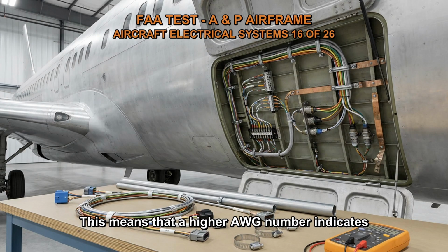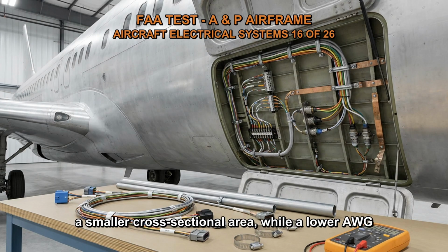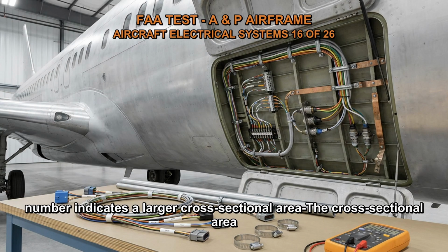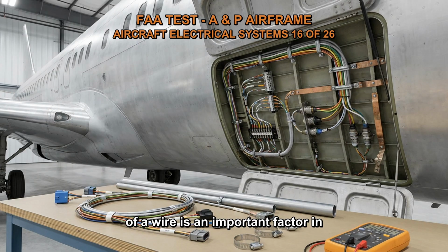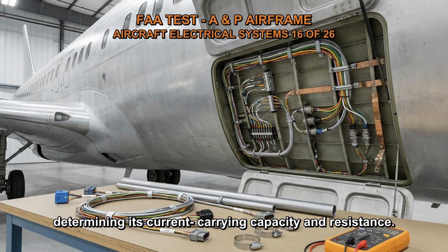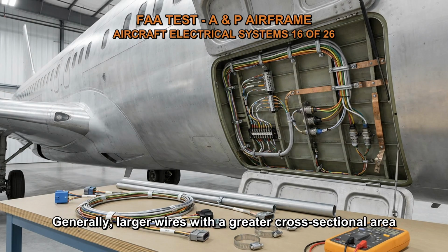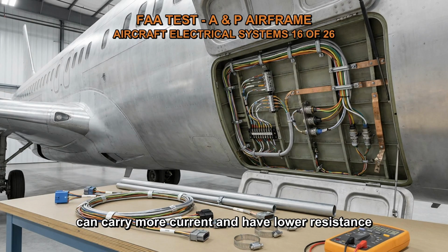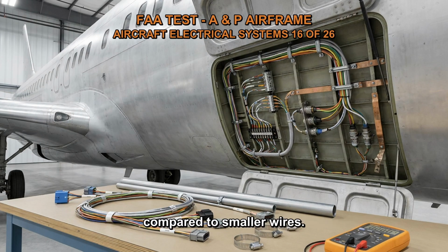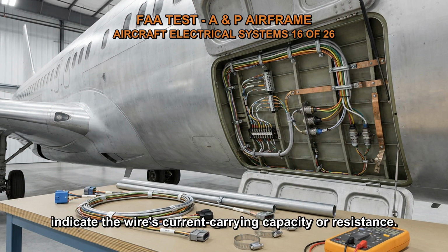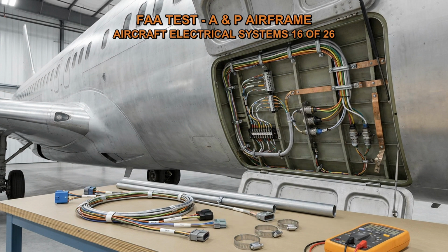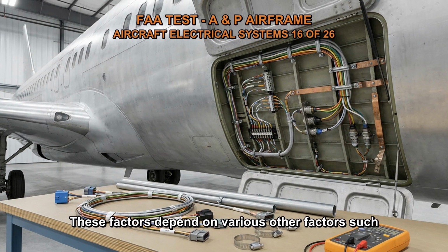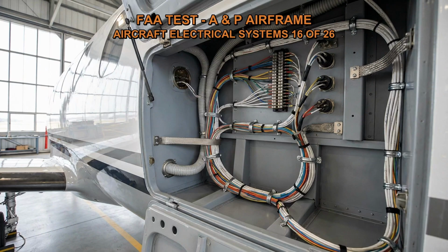This means that a higher AWG number indicates a smaller cross-sectional area, while a lower AWG number indicates a larger cross-sectional area. The cross-sectional area of a wire is an important factor in determining its current carrying capacity and resistance. Generally, larger wires with a greater cross-sectional area can carry more current and have lower resistance compared to smaller wires. However, the AWG number itself does not directly indicate the wire's current carrying capacity or resistance. These depend on other factors such as the material of the wire, insulation, and the specific application requirements.